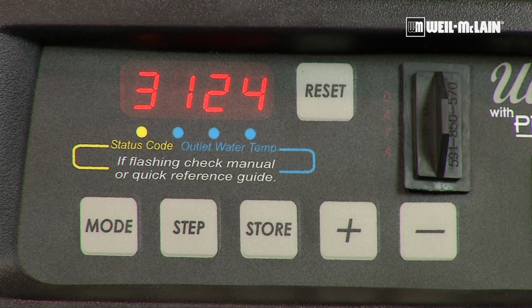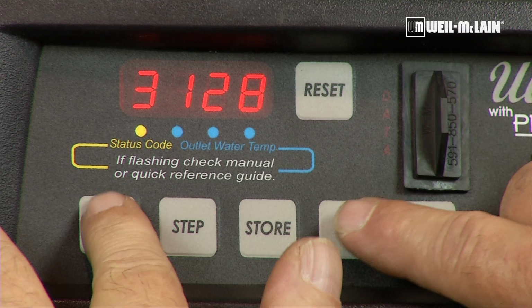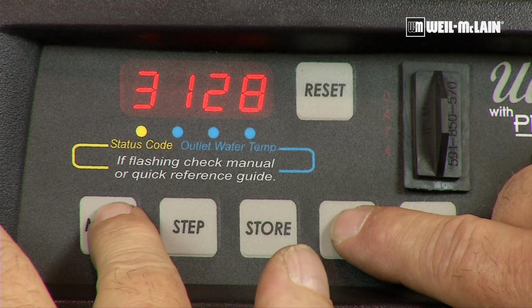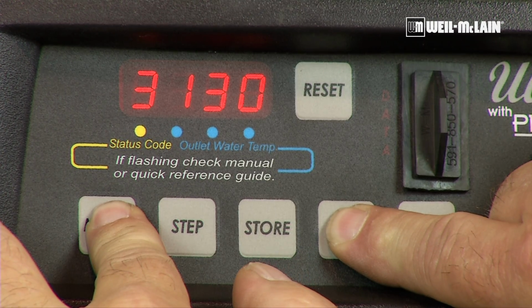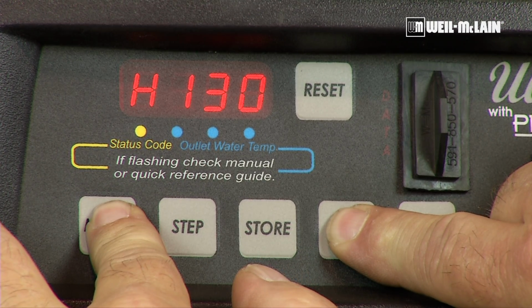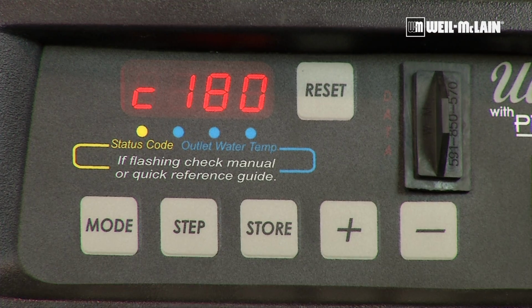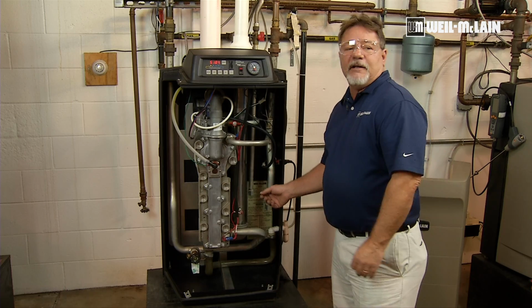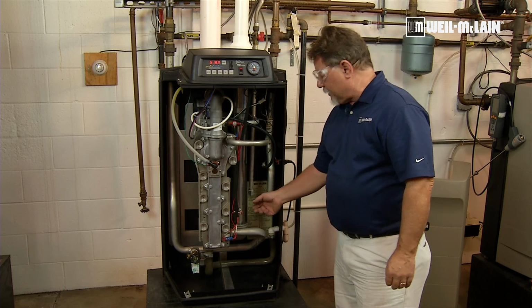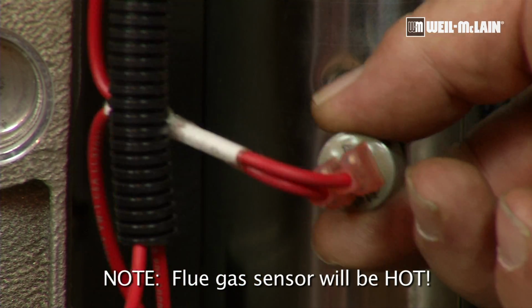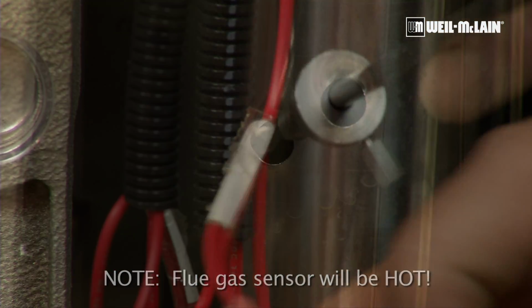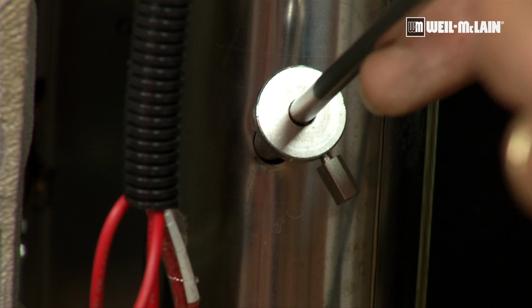What I need to do is put the boiler into high fire now, and we do that through the standby menu. I'm going to press the plus button and the mode button simultaneously. An H will appear on the left-hand side. When the H appears, we have forced the boiler into high fire. We set the boiler into high fire, so we're going to remove the flue gas temperature sensor. We're going to start our combustions.